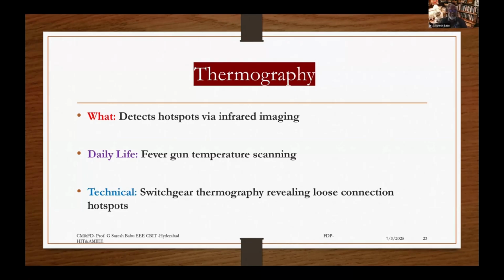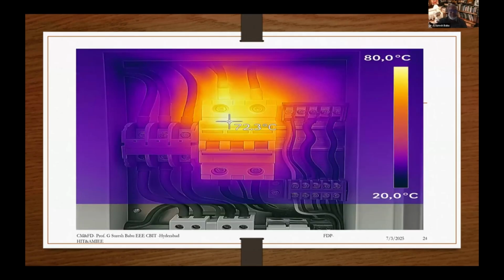Technically, switchgear thermography reveals loose connection hotspots. So this is the image; you can understand 20 degrees centigrade to 80 degrees centigrade. You find here that 72.3 degrees centigrade is the hotspot for the machine, identified by the system or the instrument. That is called a hotspot.